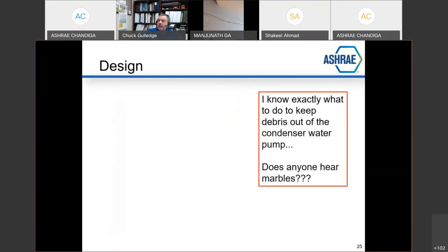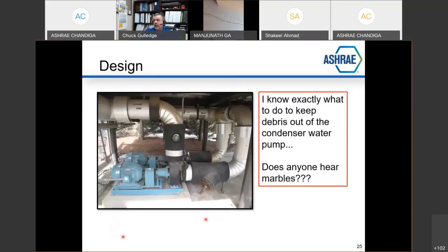I know exactly what to do to keep debris out of the condenser water pump. Does anybody hear marbles? Now, think hard about this. Marbles in a pump are a dead sign of cavitation within the pump. This is the base of the cooling tower. This is the collection off the bottom of the sumps, and it drops down and goes into these pumps and goes to the building, to the chillers. Look at these beautiful strainers located right here at the inlet of the pump.